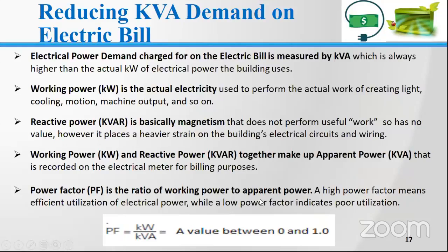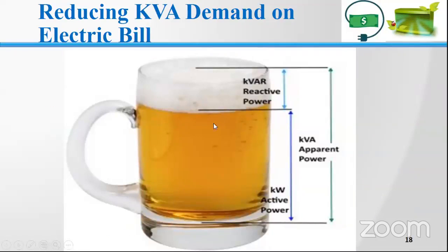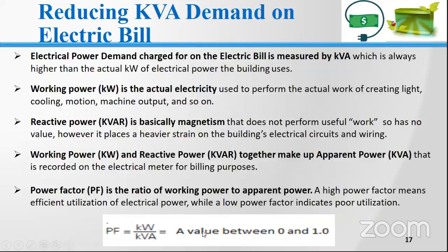What you do to deal with that is something called power factor correction. Power factor is the ratio of the kilowatts of power you use over the kVA read on the meter. The ideal is to have your kVA equal to almost exactly your kilowatts, giving you a power factor value of one.